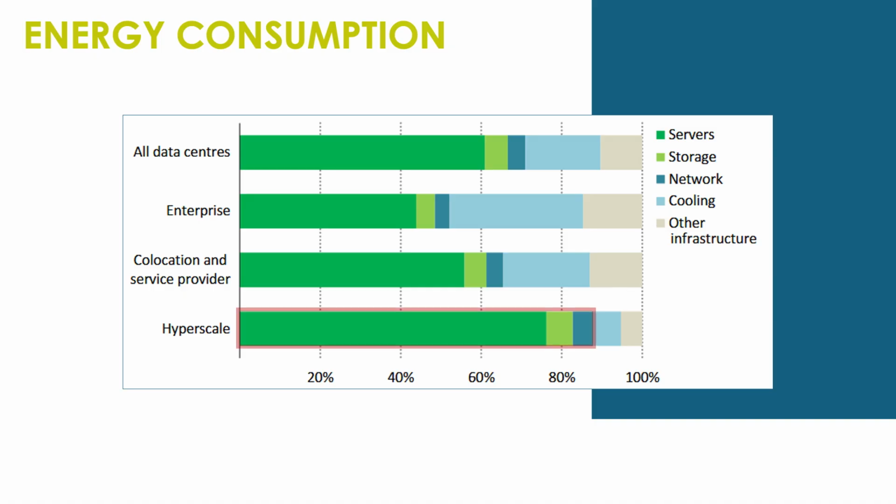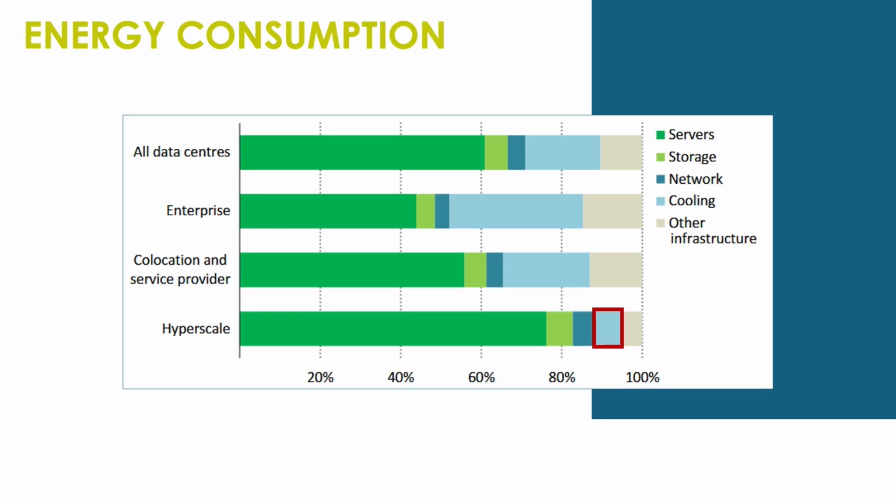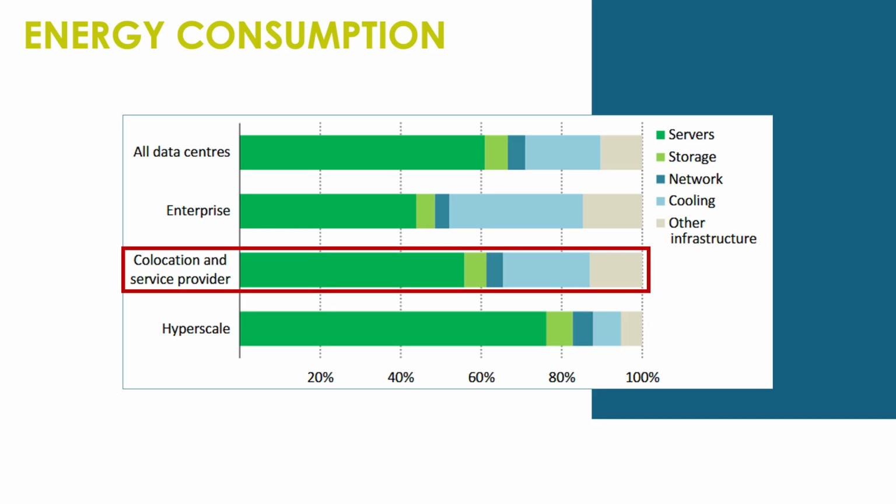On the other hand, hyperscale data centers show a very different energy distribution. These centers are designed to be efficient. Here, IT equipment can account for 70% or more of the total energy consumption. This is made possible through high server utilization, advanced workload orchestration, virtualization technologies, and highly efficient cooling systems. In such environments, cooling typically represents only around 10% of the total energy use. Finally, colocation data centers fall somewhere between these two extremes, with energy use patterns depending on the specific infrastructure and client deployment models.